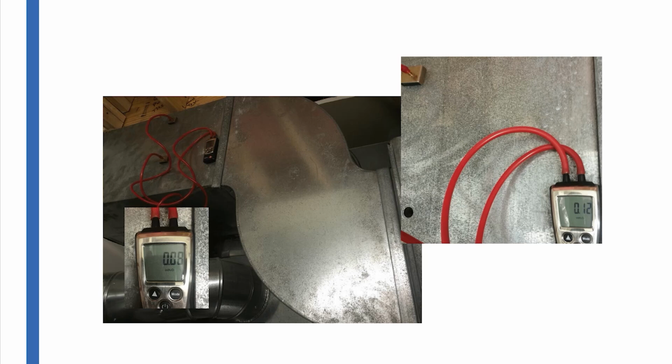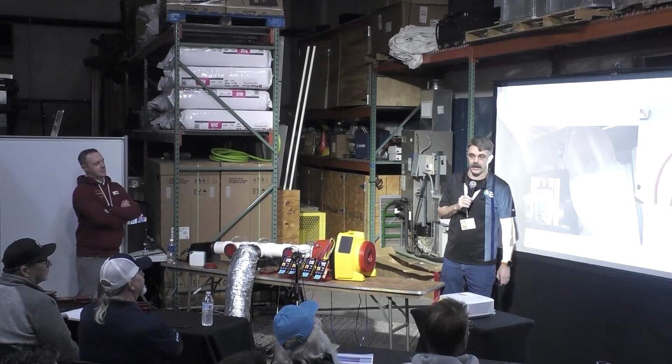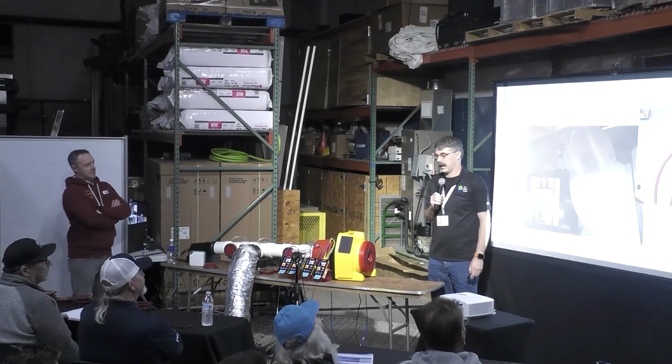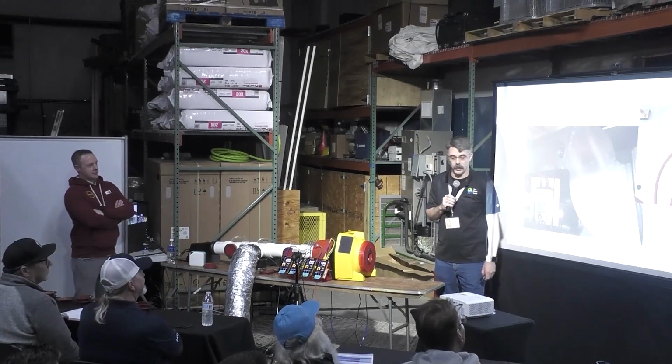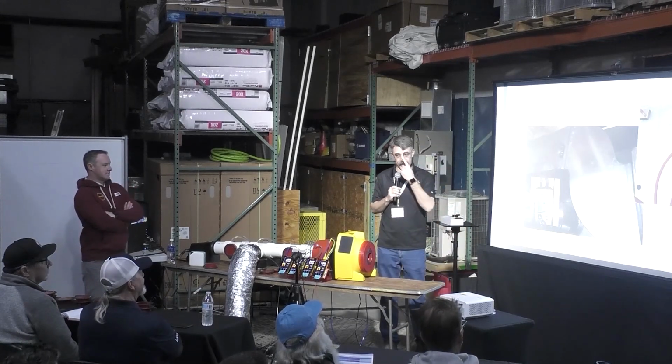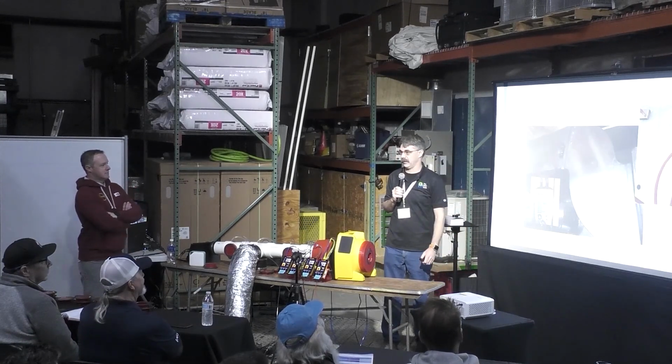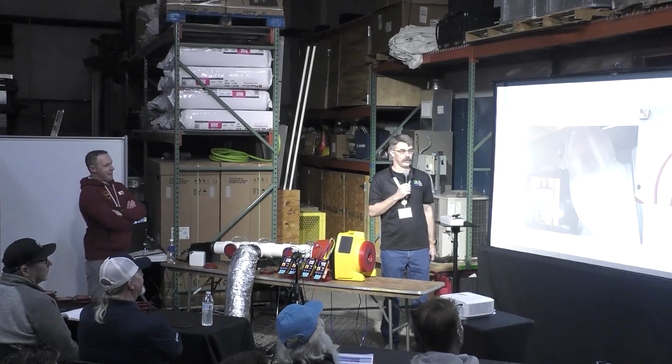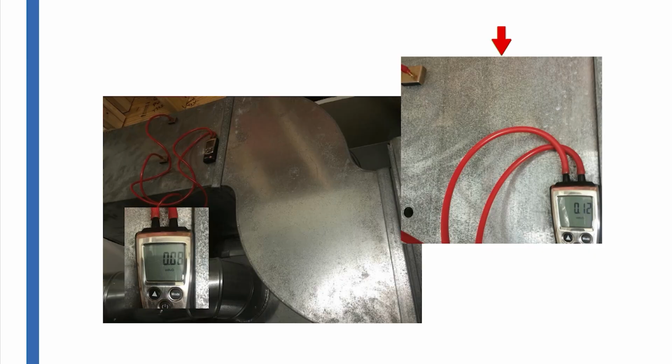So here's my illustration of this. This is one I happened to find on a trouble job where I was looking for the reason that I had a lot of static pressure in a system. I had a lot of conditioning problems. I had multiple blower motor failures on it. And they finally asked me to say, why is this failing so often? Okay, let's do some deeper diagnostics.